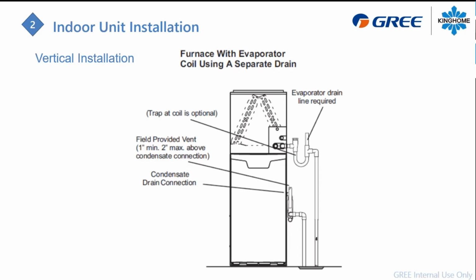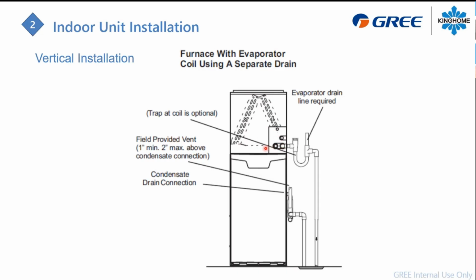So here about the drain, we're going to just focus on this little vent here. This is really important. You have a 3/4 outlet here for your drain pan. The P-trap on the picture is clearly optional. You don't have to install the P-trap, so it can be straight like this. But the important thing is when you install a case coil here in the supply air duct, you will get high pressure ventilation here. So air will push air into your drain. If it's a separate drain like this, you won't face any issue regarding your furnace.